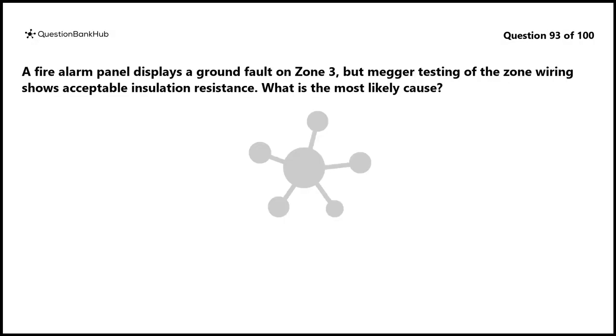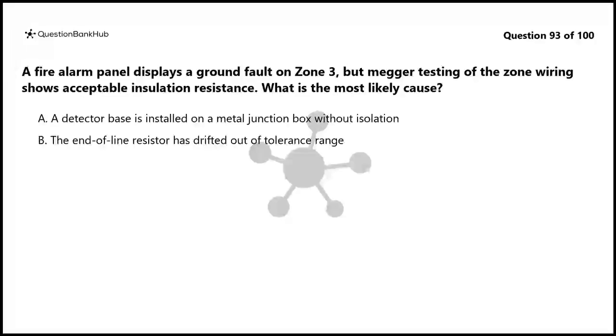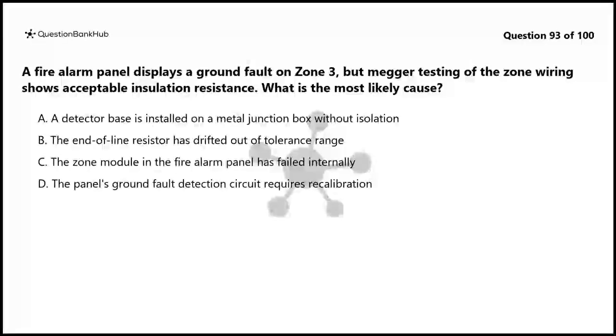Question 93. A fire alarm panel displays a ground fault on Zone 3, but Megger testing of the zone wiring shows acceptable insulation resistance. What is the most likely cause? A. A detector base is installed on a metal junction box without isolation. B. The end-of-line resistor has drifted out of tolerance range. C. The zone module in the fire alarm panel has failed internally. D. The panel's ground fault detection circuit requires recalibration.